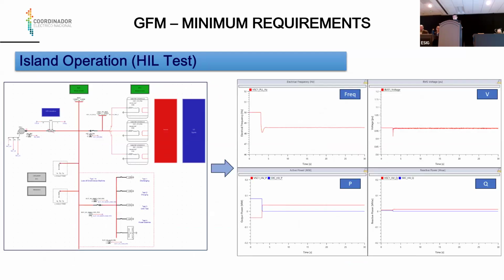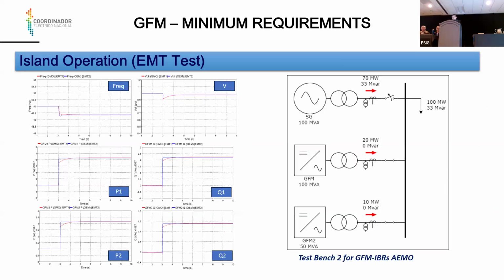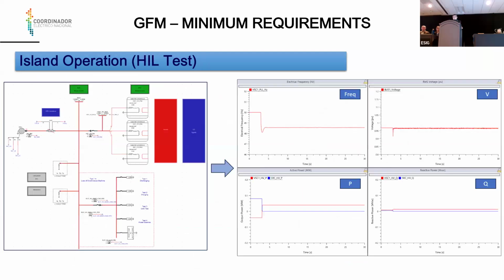Related to the control hardware-in-the-loop test, here we have just one controller, so we can't reproduce this exact test bench that used two grid forming models. But anyway, in this case, the result was very similar to the EMT simulations. The result was stable and the response was almost instantaneous and according to the grid forming expected behavior.